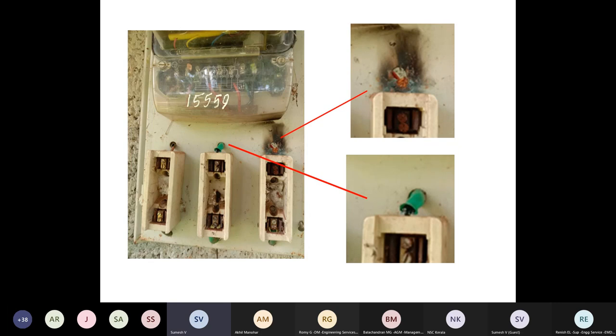Here you can see two phases, R phase and Y phase, R phase and middle phase. In the middle phase, the proper sleeve has been given, so there is no problem. But in the R phase, as no sleeve is provided, the wire comes in contact with the sharp edge of the metal object, the insulation gets damaged, and the supply comes to that metal board, and the person who comes in contact with that metal object gets shocked and electrocuted. So what should we do?